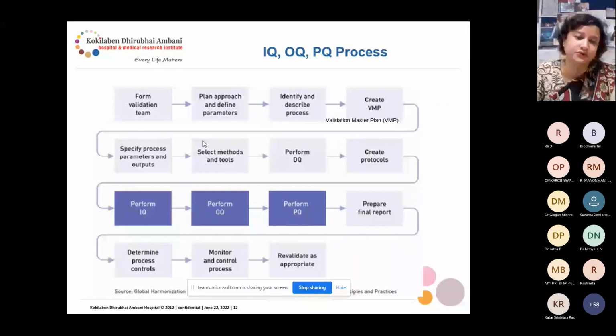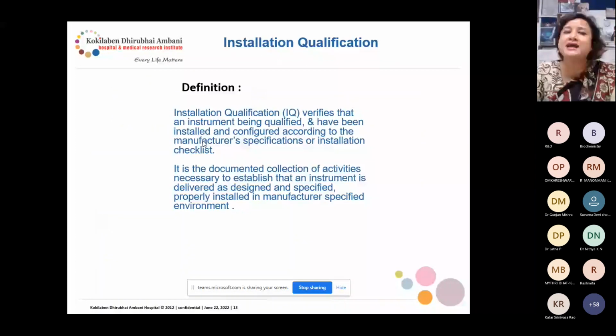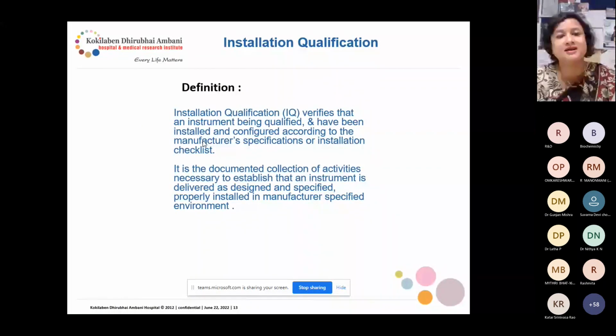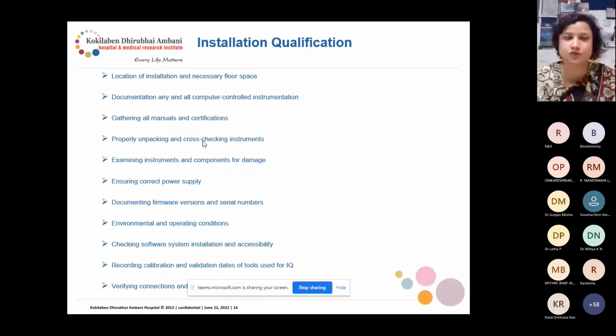So this is the total process, and IQ verifies that the instrument being qualified has been installed and configured according to the manufacturer's specifications or installation checklist. It is the documented collection of activities necessary to establish that an instrument is delivered as designed and specified, and properly installed in the manufacturer-specified environment. So what we need for that: location of installation and necessary floor space. So IQ should have this documentation too.